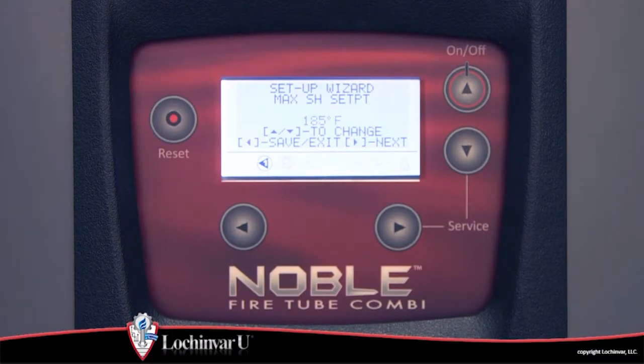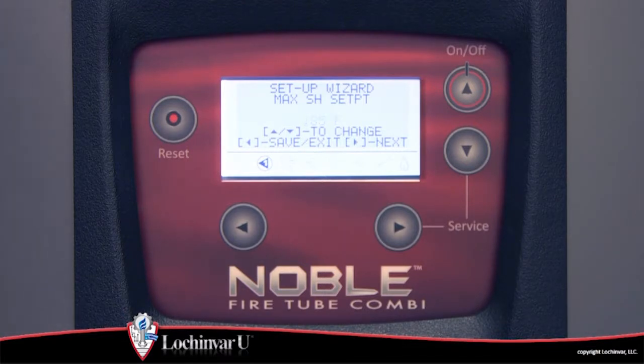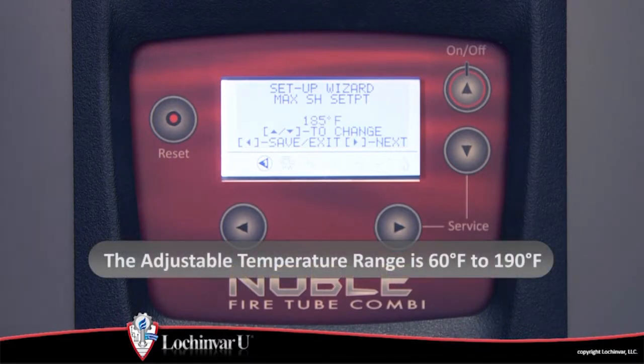It also serves as the limit for the space heat set point that can be generated by the outdoor reset curve if the outdoor temperature falls below the setting of the outdoor temperature coldest day parameter. The adjustment range for this parameter is 60 degrees Fahrenheit to 190 degrees Fahrenheit.